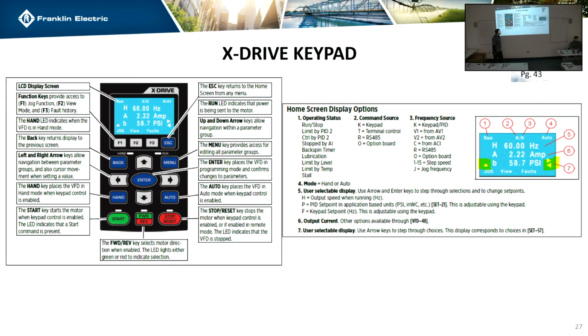And then this is a big thing for troubleshooting, just understanding what the screen is telling you. So all of these things are gonna tell you exactly how the drive is set up. Number one is your operation status. It's gonna say run, stop, fault, things like that. This is the full list. Mostly what you're gonna see is run, stopped, timer, and maybe control by PID2. I mean, all of these can come up, but mostly what you're going to see is run or stop.